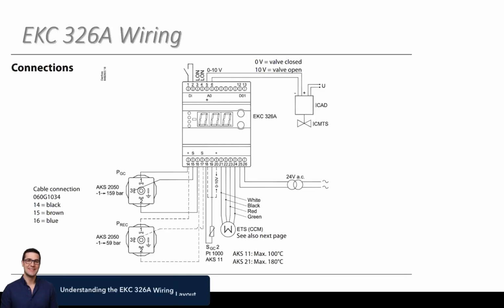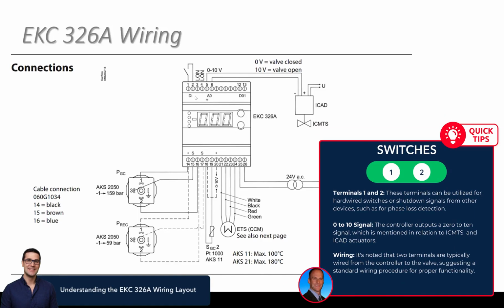Here and move on to standard kind of wiring layout for it. Again, just kind of start along the top and then we can move down to the bottom. There is a main switch we haven't talked about yet, but terminals 1 and 2. If someone wanted a hardwired switch or maybe a shutdown signal from another device and they wanted to use that to shut down the EKC, maybe a phase loss, for example, there are terminals that can be used for that on 1 and 2.